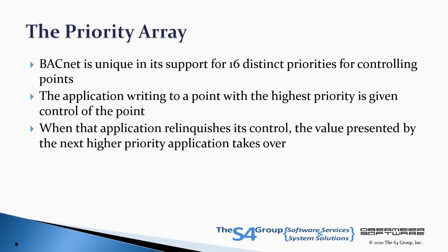The BACnet Priority Array functionality is unique. We know of no other communications protocol that provides a similar capability. The Priority Array allows multiple applications to work with any data point in a completely deterministic manner.